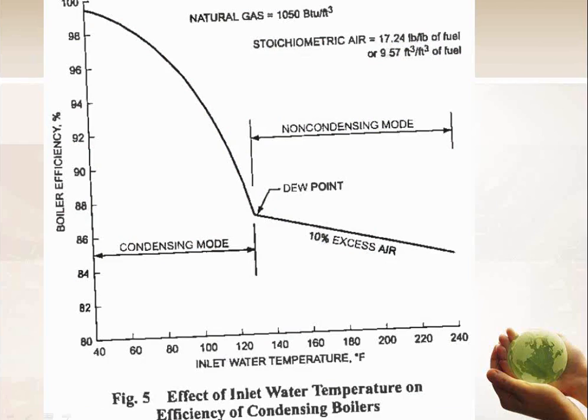So what we've got on this particular chart is, down on the bottom, inlet water temperature to the boiler. So this is my return water, from 40 to 240 degrees in this particular chart. And up the left, I have boiler efficiency, and this chart goes from 80 to 100% in this case. Right, so normal boiler return water temperature is typically 160 degrees in a normal system.